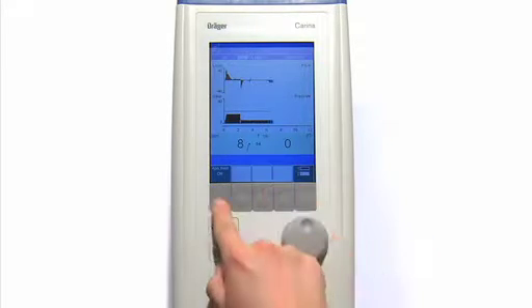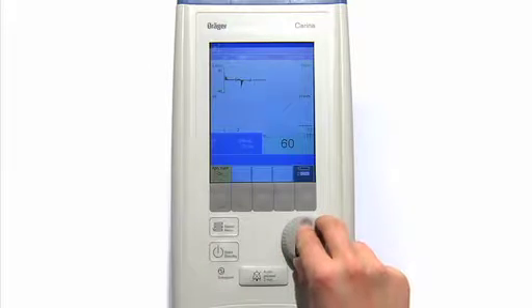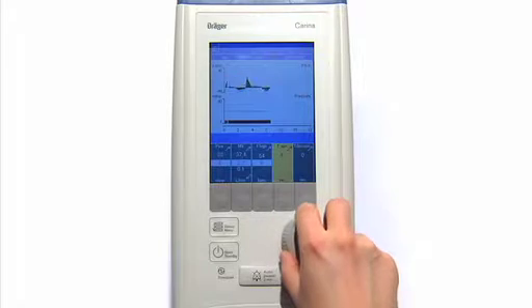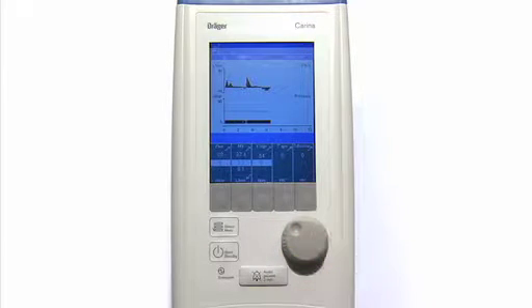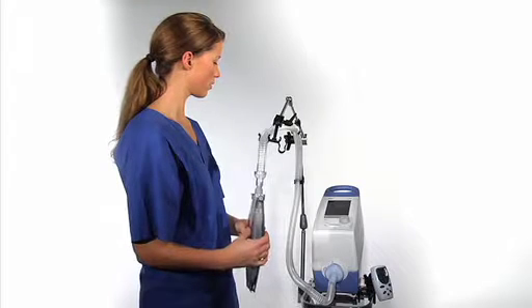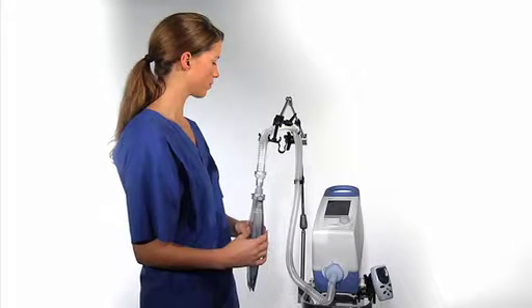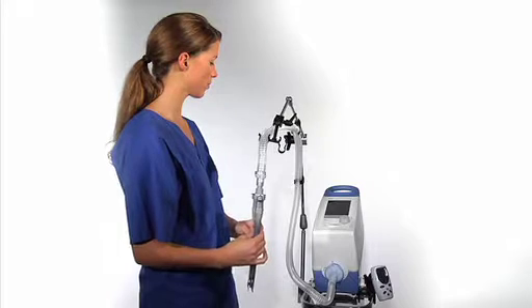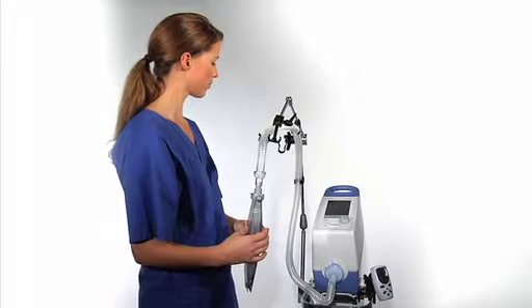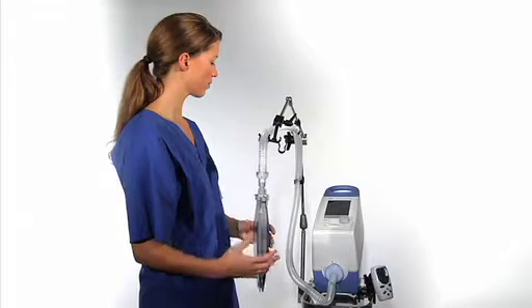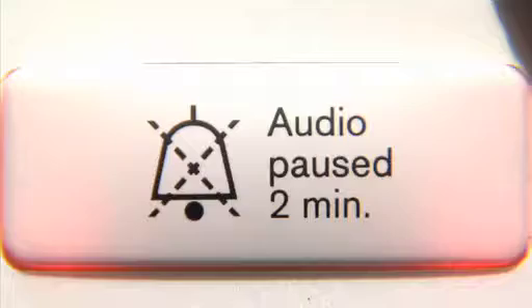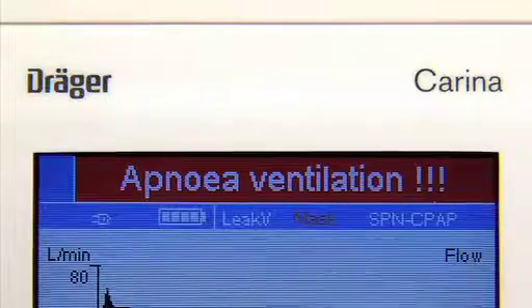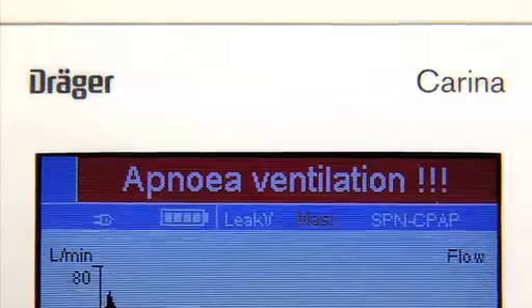Settings: apnea ventilation on. Alarm T apnea: 5 seconds. The alarm T apnea allows the user to determine the apnea alarm time and the apnea ventilation start time. Now mimic a spontaneously breathing patient by pressing the test lung. When you stop spontaneous breathing, the alarm apnea ventilation will appear after 5 seconds and the apnea ventilation will begin.